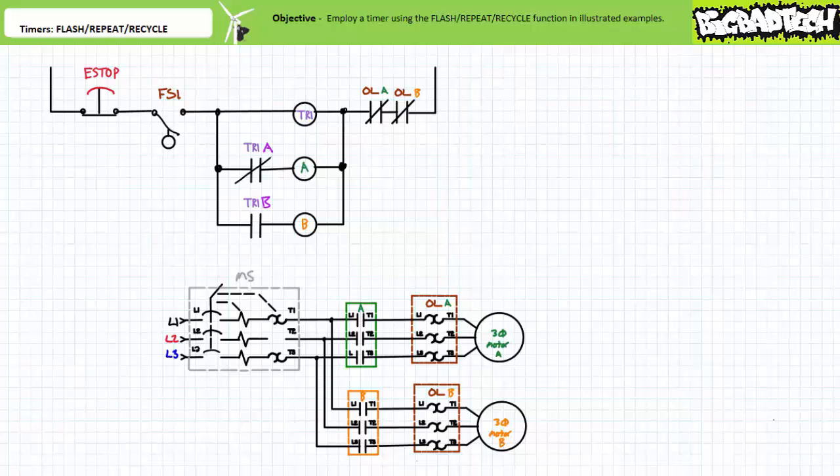For this simple example, note that the series nature of the normally closed overload contacts serves to de-energize both motors whenever one motor experiences a sustained overload condition. Even though the other motor may be fine, this system would still cease pumping the tank. For this reason, if this was some mission-critical task that must be accomplished, it would necessitate a significant upgrade in the existing ladder logic to time-share while both motors are available, and shift solely to the available motor if the other ever entered overload conditions.